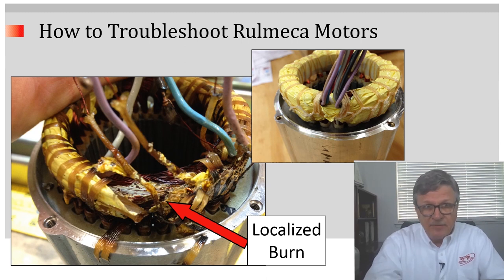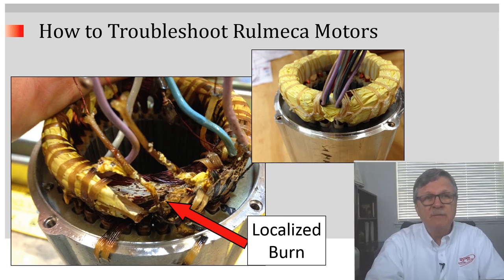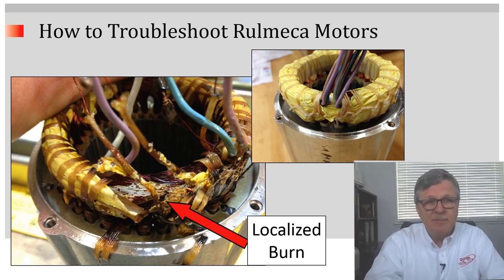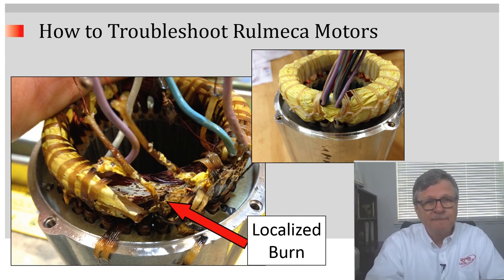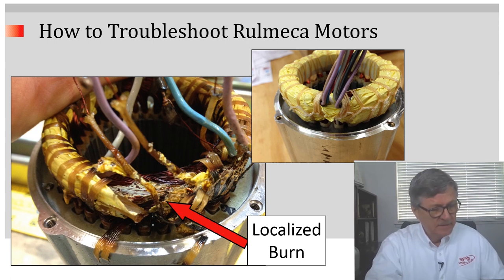This photo was taken after a 230-volt motor was put into service on a 460-volt supply. It is still a localized burn, but it is not a pinprick. So these are two examples of overvoltage damage.